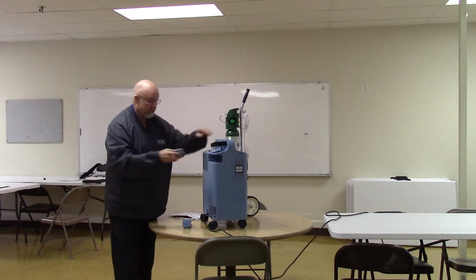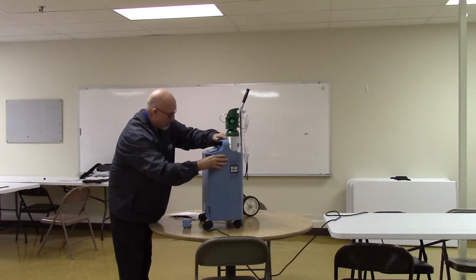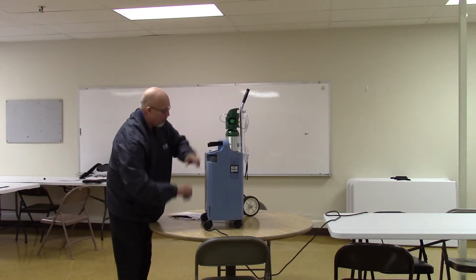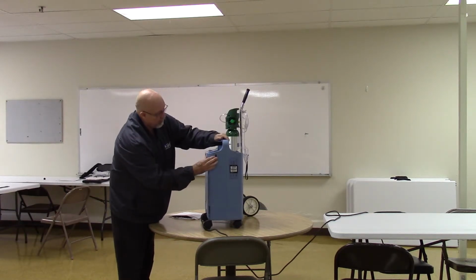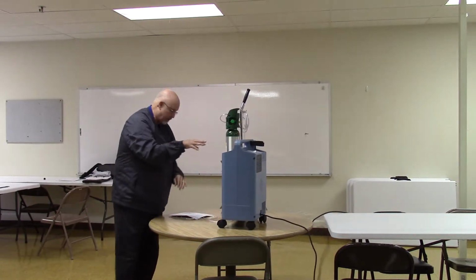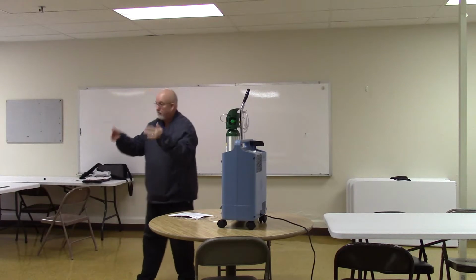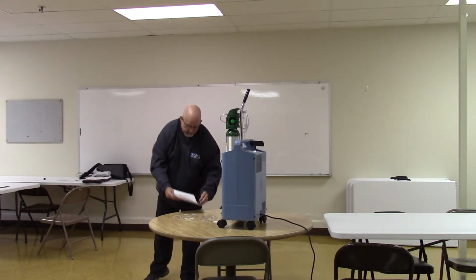But you guys don't need to change what we call a cabinet filter anymore with these newer concentrators. You may have some older ones that you do have filters on. I'm not familiar with your building enough to know if all you have are the EverFlo blue ones, or if you have some old ones with filters on the side. Those need to be cleaned. We'll talk about that in a little bit.